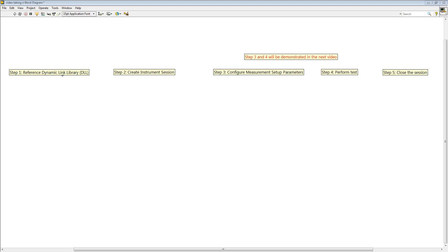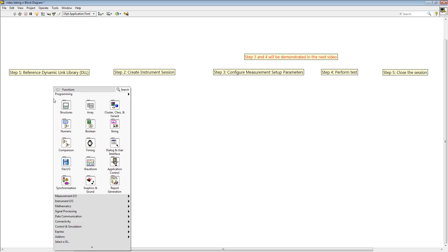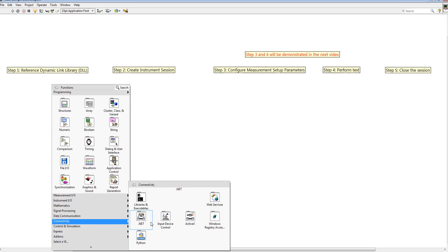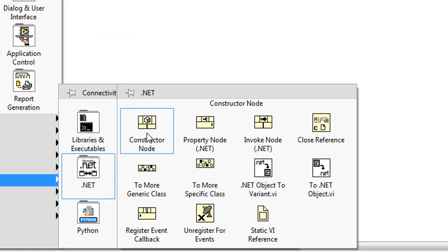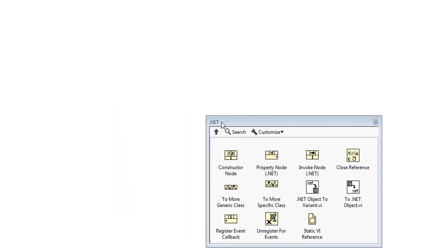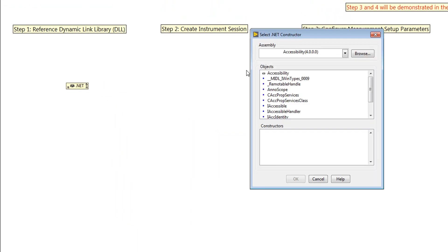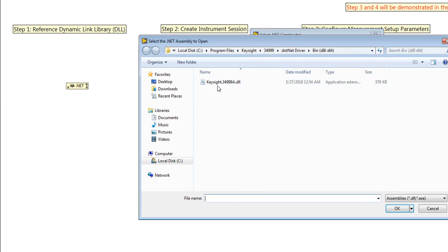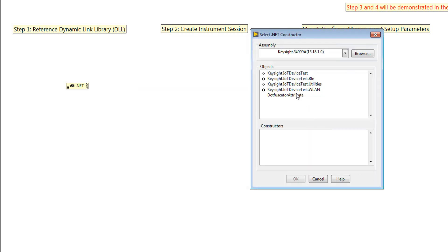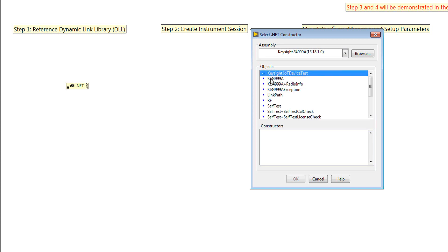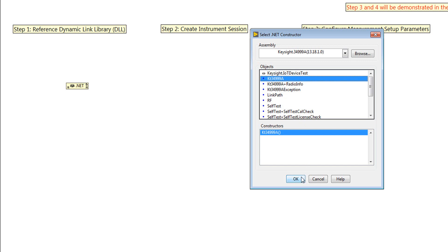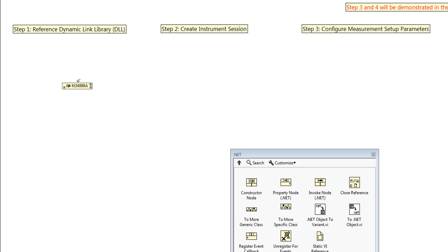First, to reference the DLL into LabVIEW, right-click at the block diagram, find Connectivity, then .NET, and select the Constructor Node. You can use the pin button to create a window for this. We create a constructor node, browse the DLL, and find the DLL that you want. Click and select OK. You can see the Keysight IoT device test here. Expand it and find Kt34999A, then click OK. This is the instance we created — that completes step 1.